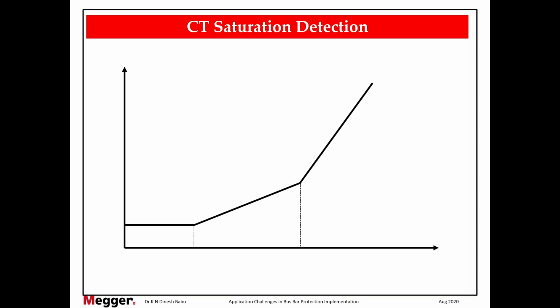Just look at this. This is the biased differential curve where ID, differential current, is plotted here. IR, restraint current, is plotted here. We have the minimum current here up to breakpoint 1. After breakpoint 1, breakpoint 2. So between these 2 points, it is slope 1, and after that, it is slope 2. Now, this is a well-known concept. I'm not discussing this. This is just to recall it step by step.